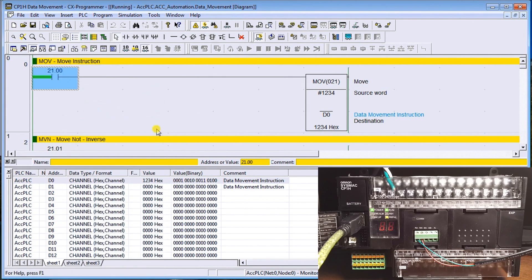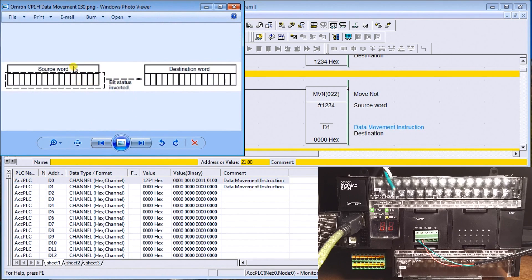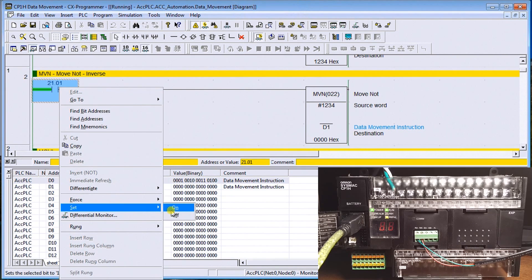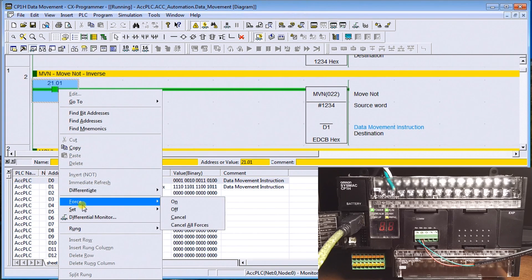Next is Move Not (MVN). What it does is take the inverse of whatever is in the source word and put it into the destination. In our case, it takes the number 1234 — whatever bits are on in those 16 bits — inverts them, and puts the result into data memory one. Turning it on, it puts the number EDCB into data memory one, which is the exact inverse of 1234.